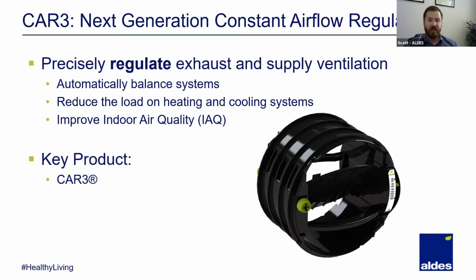So by controlling what can go into my vertical shafts, specifically risers and things like that, by controlling the pressurization of the building, I'm going to reduce the load on my heating and cooling system. Well, heating in the winter and cooling in the summer, because you're still going to have these challenges in the summer as you have operable windows and doors, people open up their balconies. You're going to have this big swing in airflow, and your DOAS system, your makeup air system, is going to have a difficult time trying to compensate, and then going to be putting a lot of extra energy into those systems.